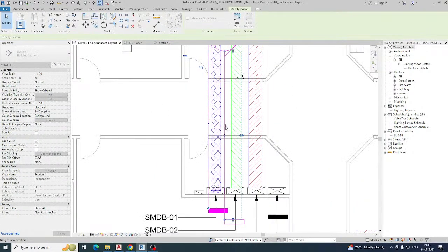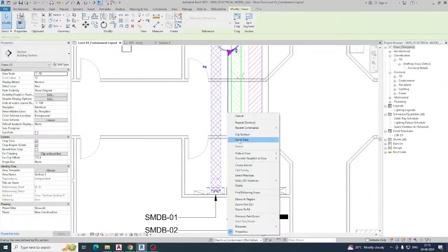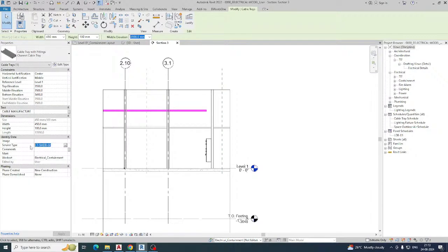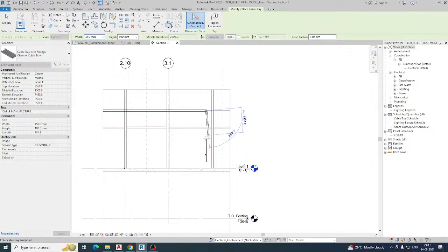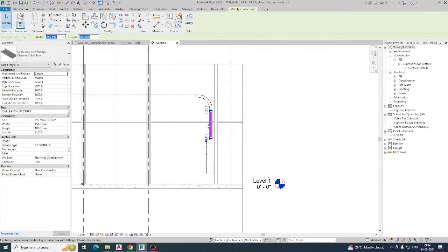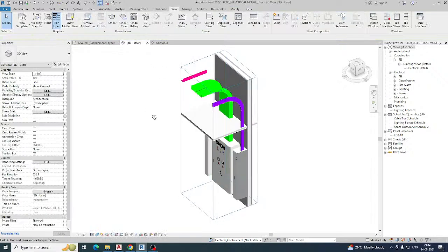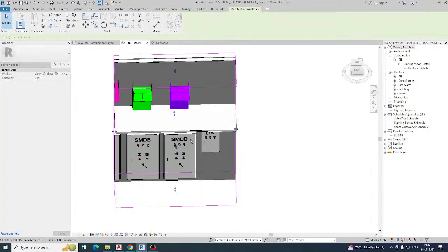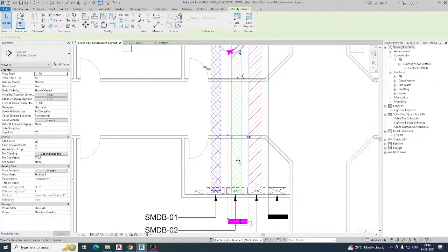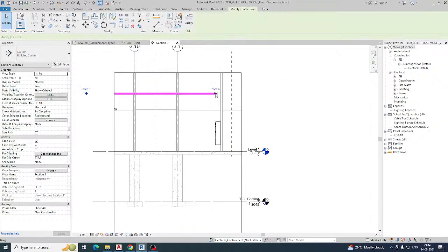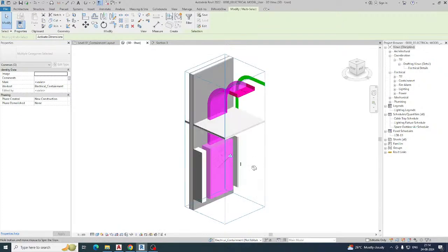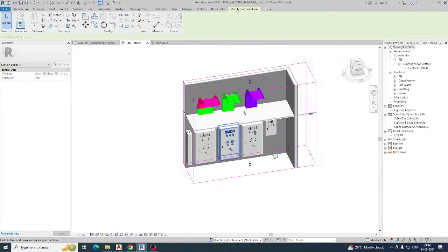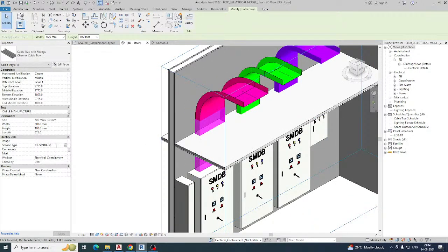For another containment drop to another panel, go to the view and draw another cable tray for service 02. Use Create Similar or draw cable tray, set the service to 02, and pick the cable tray route. The same filter will apply and you can see it in the 3D view. Repeat for a third cable tray — if it's showing the wrong color, change the service type from 2 to 3 so the color updates automatically.